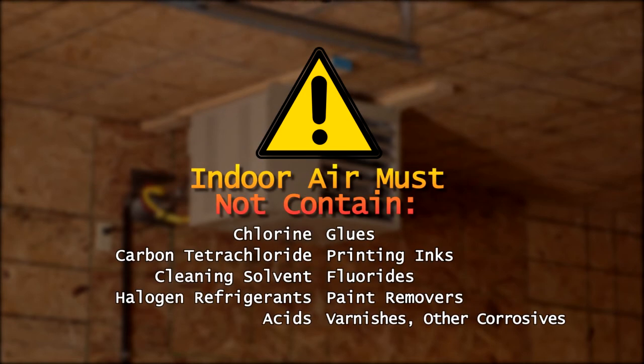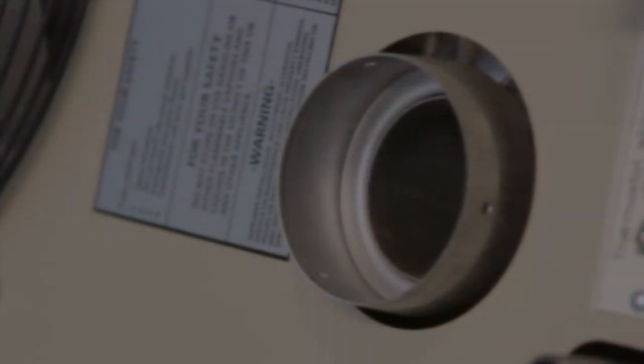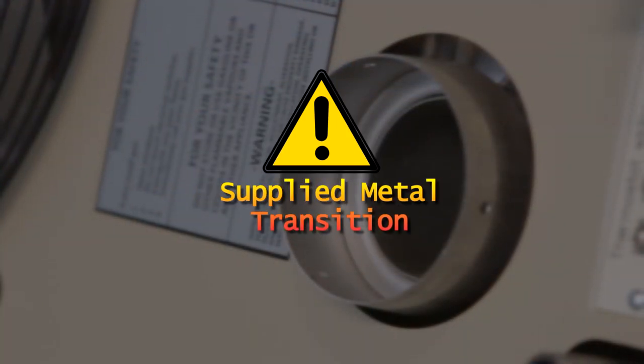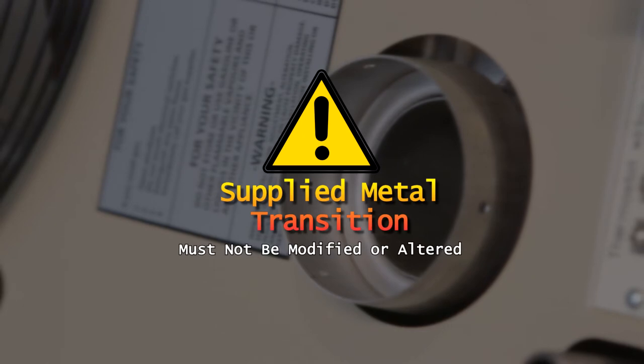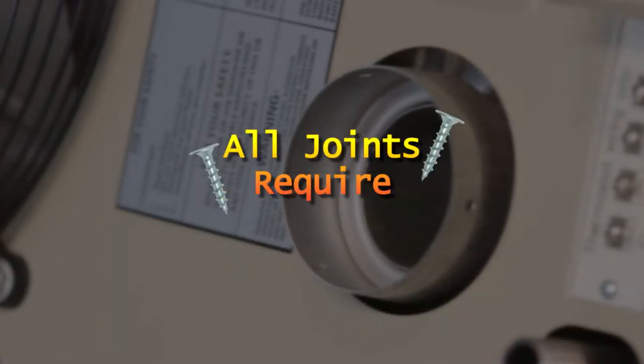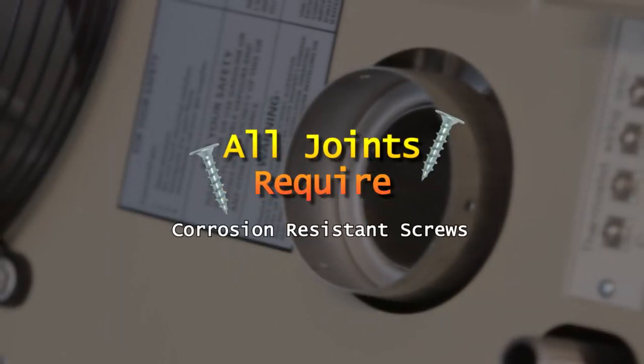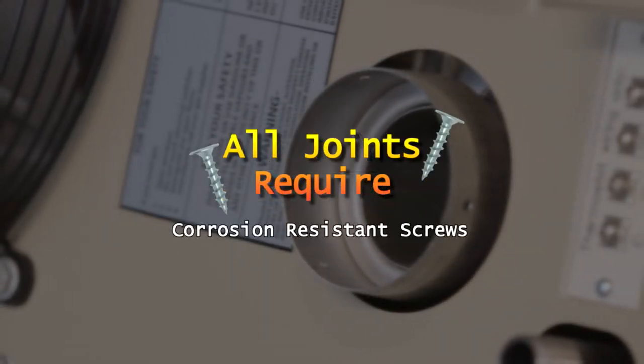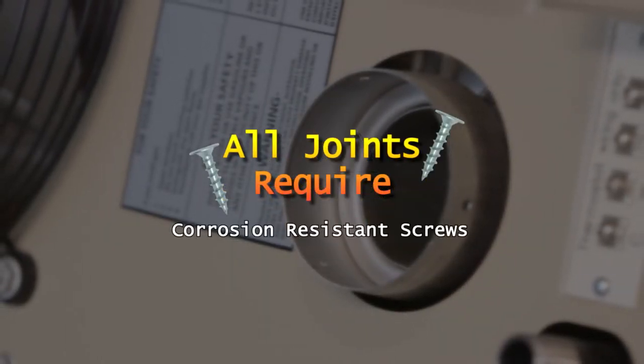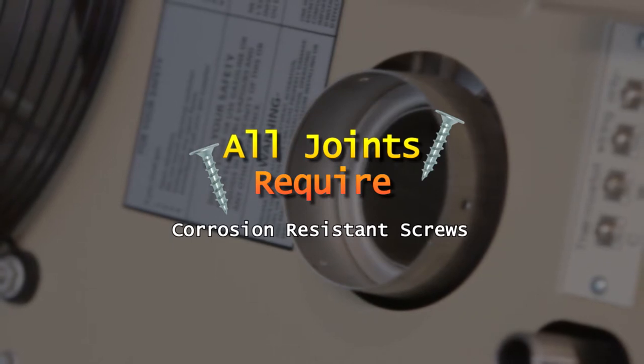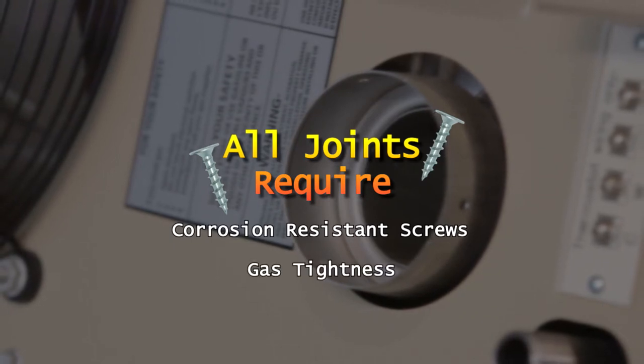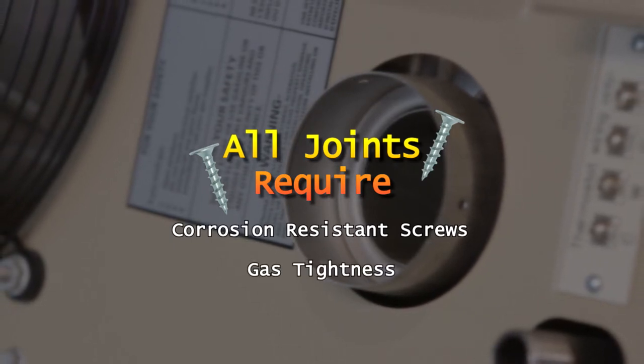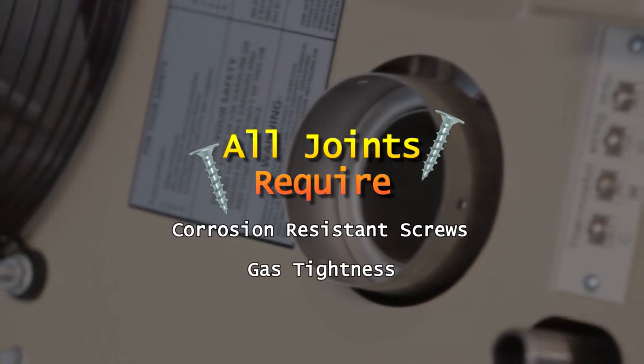If indoor air will be used for combustion, it must be free of contaminants to avoid reduced unit lifespan. The metal transitions applied with the certified unit must not be modified or altered, and all joints must be secured with at least two corrosion-resistant screws and checked for gas tightness after installation.